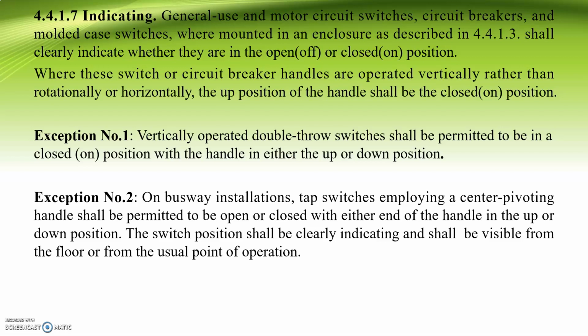Chapter 4.4.1.7, indicating. General use and motor circuit switches, circuit breakers, and molded case switches, where mounted in an enclosure as described in chapter 4.4.1.3, shall clearly indicate whether they are in the open or off, or closed or on position. Where these switch or circuit breaker handles are operated vertically rather than rotationally or horizontally, the up position of the handle shall be the closed or on position. Exception number 1: vertically operated double throw switches shall be permitted to be in a closed or on position with the handle in either the up or down position.